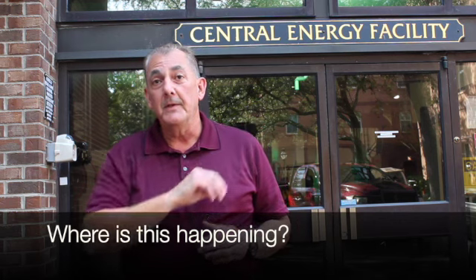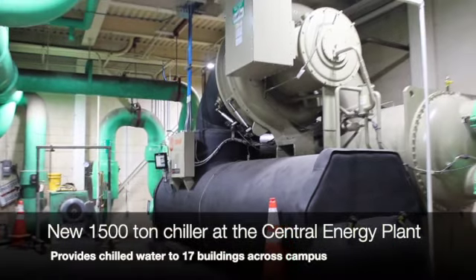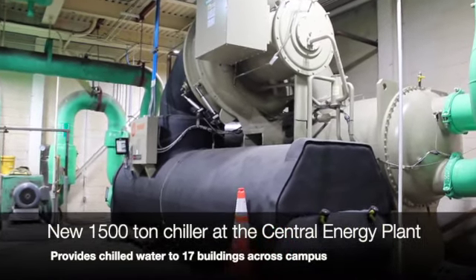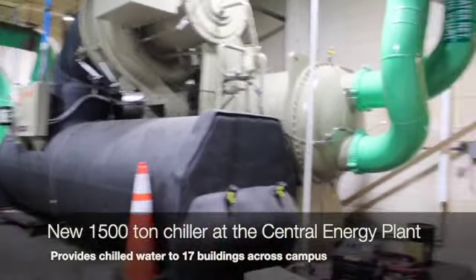We put in a new 1,500-ton chiller. We're rebuilding our economizers on our boilers. We'll pick up 5% efficiency on our boilers by doing that. We're gaining quite a bit off this new chiller. Cost per kilowatt per ton is a lot less with the new chiller than it was with the old one, so we're conserving a lot of energy.